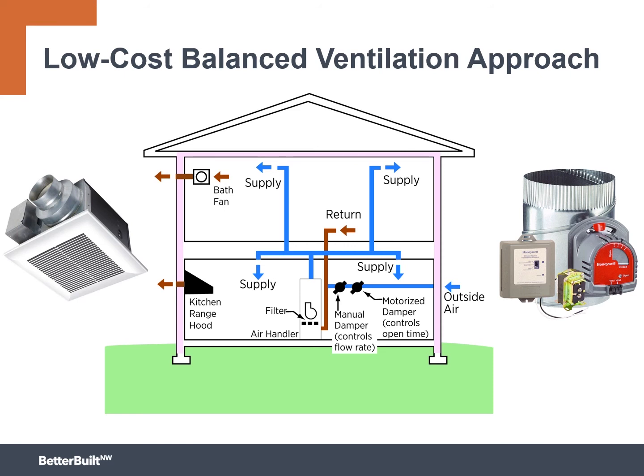You can do this intermittently, meaning it comes on and it comes off. But I've talked about that math, and we're going to go through it again, because you'll pretty quickly realize the size of fans and the speed you need to run your central air handler may make that not really the kind of solution you're looking for. If you can figure out a way to do this continuously, again, with an Energy Star exhaust fan, an ECM 2.2 or higher central air handler motor, commissioning them to be within 10% of the supply and exhaust, and then run them continuous, that is your best low-cost bet for balanced ventilation.